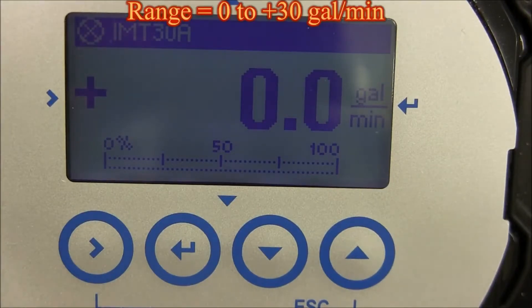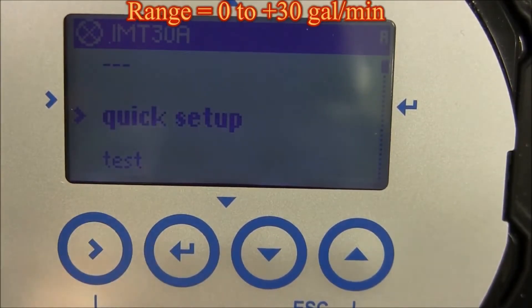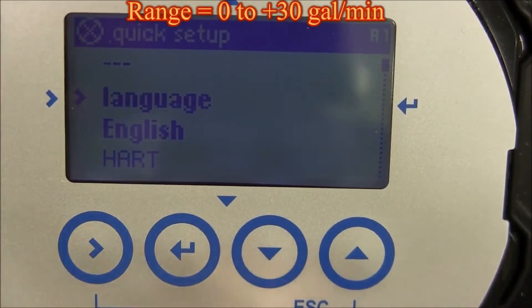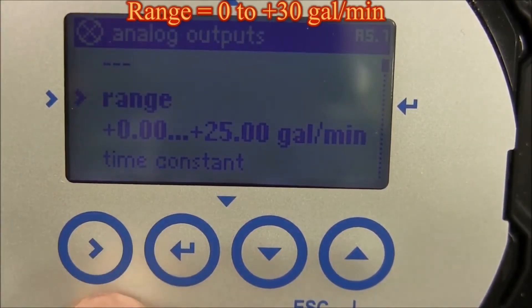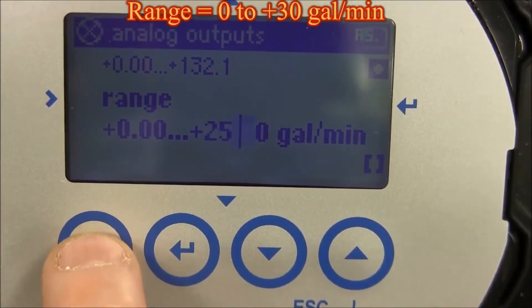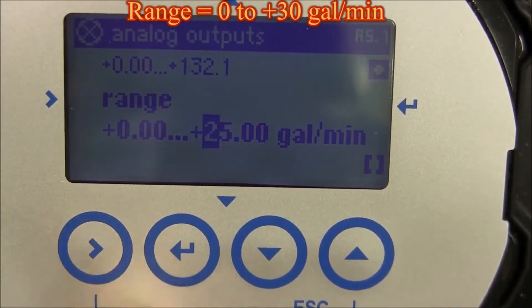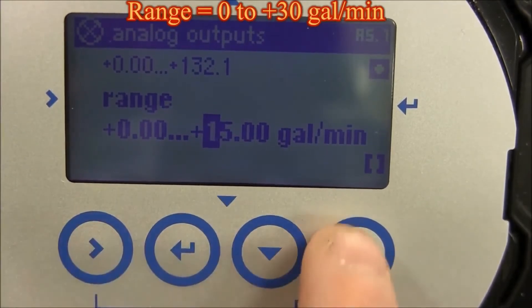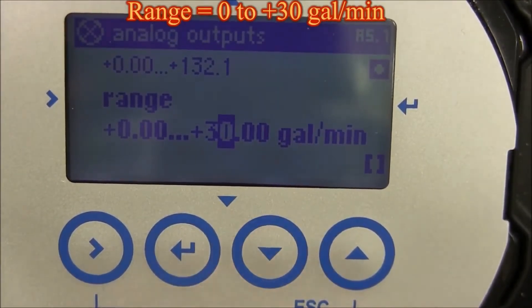To use zero to thirty gallons per minute as your range setting, press and hold the right arrow for three seconds, then let go. Press the right arrow to go into quick setup. Use the up or down arrow until you see analog output, then press the right arrow. Press the right arrow to go into range. Use the right arrow to scroll to the number you want to change. In this case, go to the two and change that to a three, then go to the next number and change that to a zero. Keep doing this for all the numbers until you get zero to thirty gallons per minute shown.